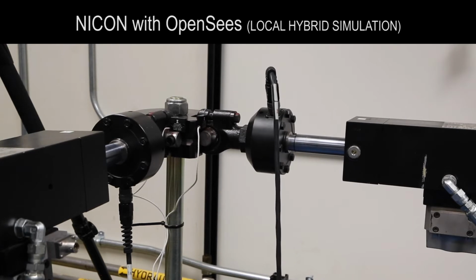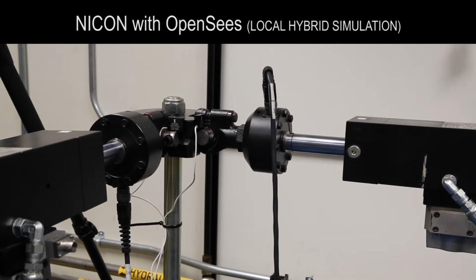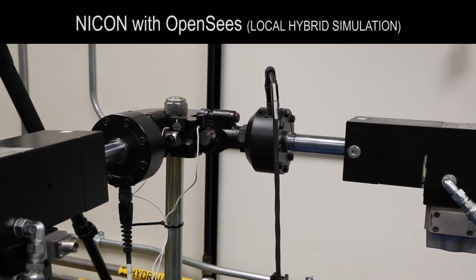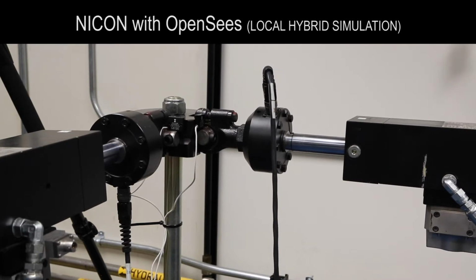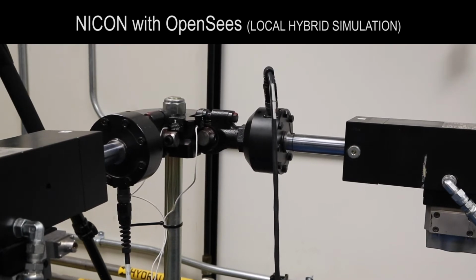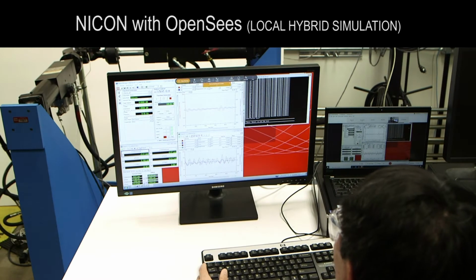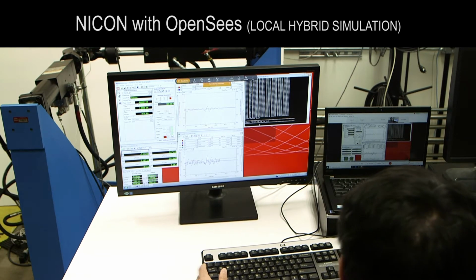So the test will progress. Now we are at step number 400-something. At 500, it will stop. Okay, as you can see now, at step number 500, as we defined, it finished the hybrid simulation, and NICON has a display message showing the communication is done, and now we can stop it.